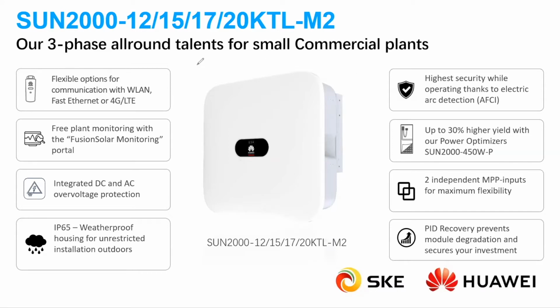In regards to communication with the monitoring platform, you can use dongles, the WLAN dongle or the 4G dongle in case you don't have a router. These PV plants that use these types of inverters can be monitored in our free-to-use monitoring platform, which is called FusionSolar. And we just launched a new version 7.0. All our inverters have DC and AC surge protectors to protect against overvoltage. The inverters are IP65.